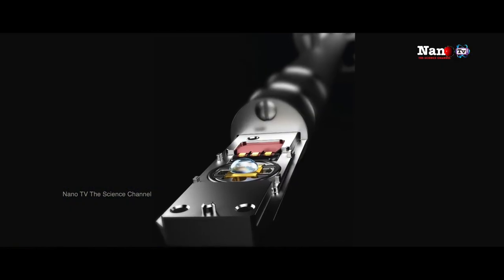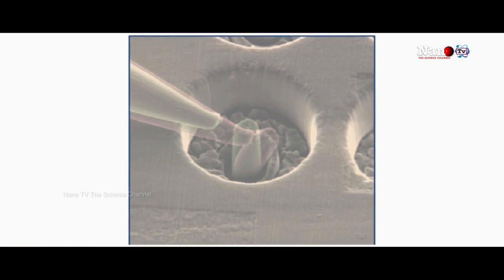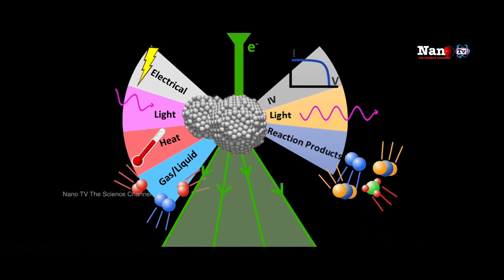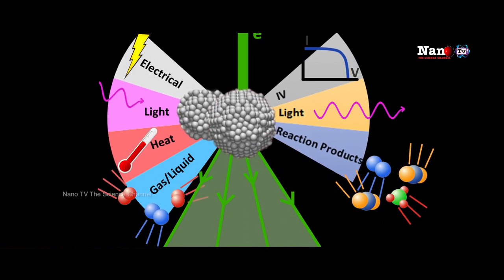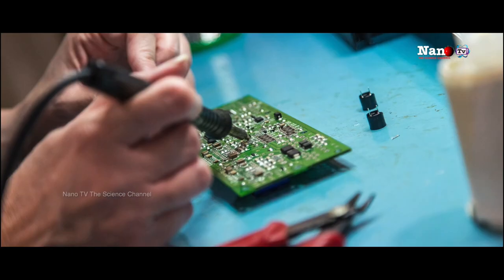Another important area is in-situ microscopy, where it is very important to understand what is happening inside the sample while it is in the machine. This is a concept developed about 15 years back. Inside the SEM, we can put a heating chamber and a cooling chamber. We can heat the sample up to 1000 degrees centigrade and cool the sample down to minus 170 degrees centigrade. The whole industry is now trying to use very fast heating and cooling to change and understand the structure.